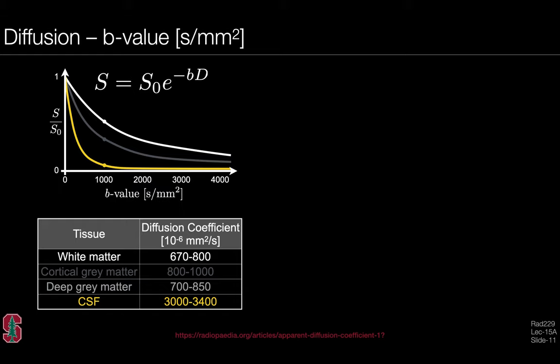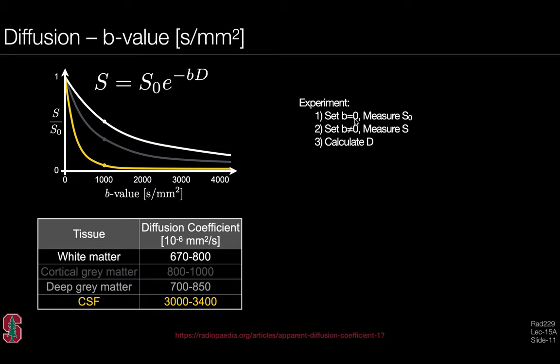Returning to the signal equation: the signal depends on a base signal S0 weighted by an exponential that depends on the B-value and the underlying diffusion coefficient. We can map different exponential decay curves for white matter, gray matter, and CSF. To measure or estimate the diffusion coefficient, two experiments are required: first, set B=0 to measure the S0 or non-diffusion-weighted image (the B0 image); second, set B to a non-zero value to acquire the diffusion-weighted signal. From these, the diffusion coefficient can be calculated on a pixel-by-pixel basis.